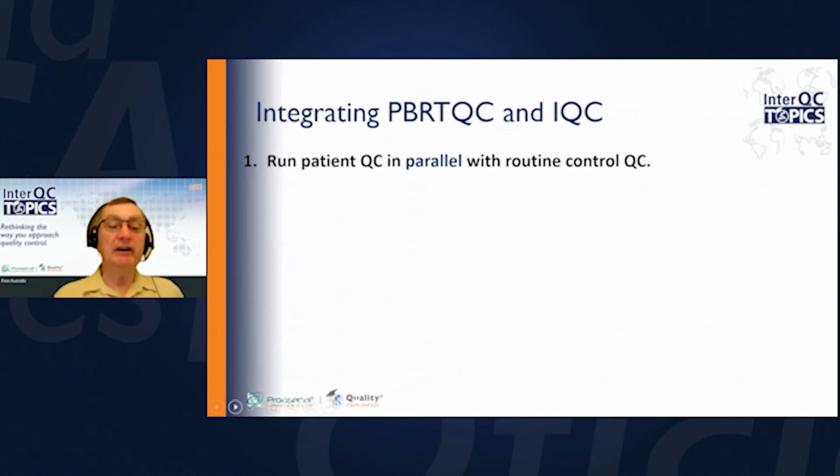The other thing about integrating patient-based real-time QC is how do you integrate patient-based real-time QC and conventional QC? You can run them in parallel, so run both patient-based real-time QC with routine QC. That's what most people are doing now, because we still need to get confidence that the patient-based real-time QC will tell us stuff and be as good as a conventional QC.